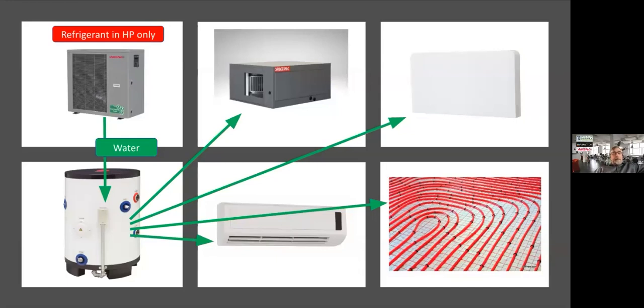So in the upper left-hand corner, refrigerant is in the heat pump outside of the building only. From that point forward, the connection is all water to a small buffer tank inside the building. And this could be a single family, it could be a multifamily. The heat pump and the buffer tank are constantly communicating, and the heat pump is charged with keeping that buffer tank at a fixed temperature. That temperature could be a warm temperature, it could be a cold temperature. It depends on if we're heating or we're cooling.